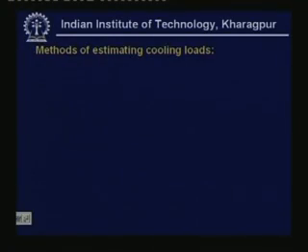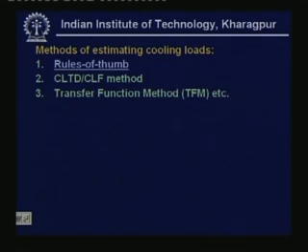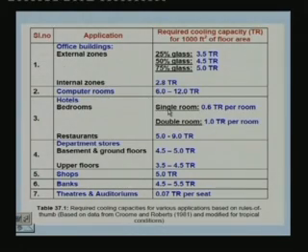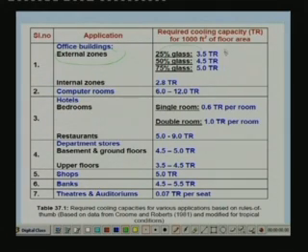Let us look at the methods of estimating cooling loads. The easiest method is based on rules of thumb; others include the CLTD and CLF method and the transfer function method. This table shows the required cooling capacity for various applications. For example, for an office building in an external zone with 25 percent glass, the required cooling capacity is about 3.5 TR per 1000 square feet of floor area.